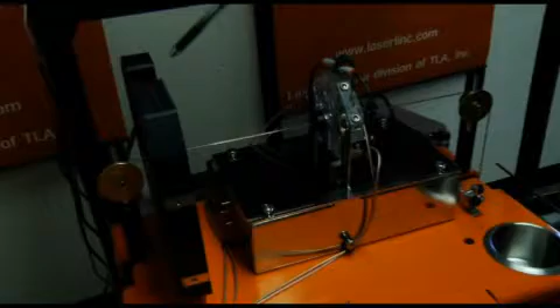This is the cross-section of a piece of tubing that is actually being dragged through 2 sensors here. One is a laser micrometer, a triple beam laser micrometer tracking the outside dimension of this tubing. This one is an ultrasonic sensor using 4 different transducers capturing the wall thickness of that. By combining the outside dimension with the instantaneous wall thickness, we're able to determine the ID as well.